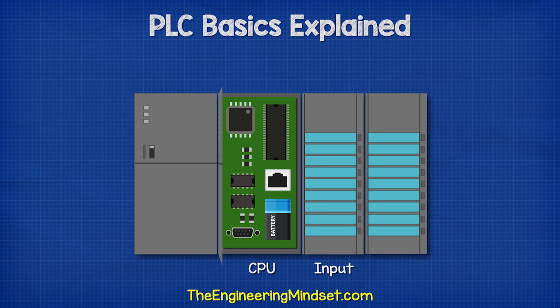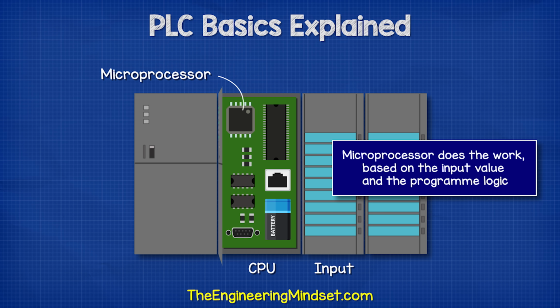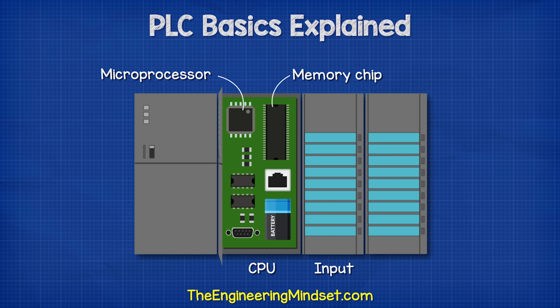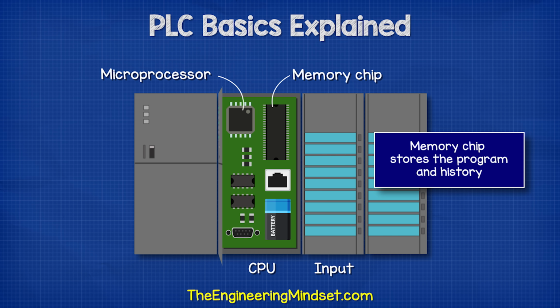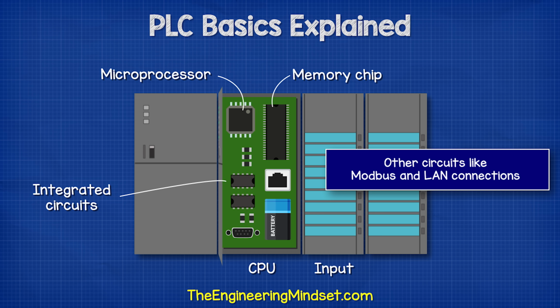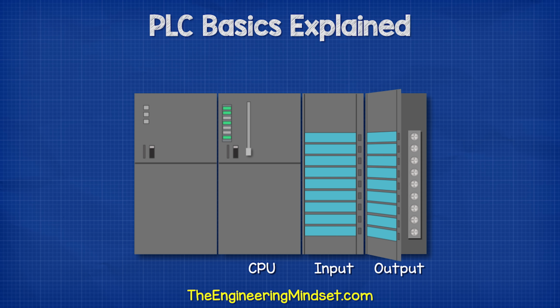The CPU, or Central Processing Unit, is the brains of the operation. It holds the program or software that decides what outputs are required by applying rules to the input signals. The CPU typically consists of a microprocessor, which does the work based on the input value and the logic in the program, a memory chip to store the program. This will also store the output history, any faults or alarms, etc. Then we also have other integrated circuits. These can be things such as Modbus and LAN connections, which allow us to remotely communicate with, reprogram, or even monitor the device.